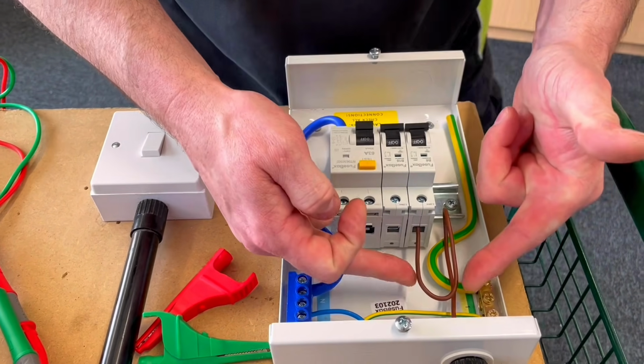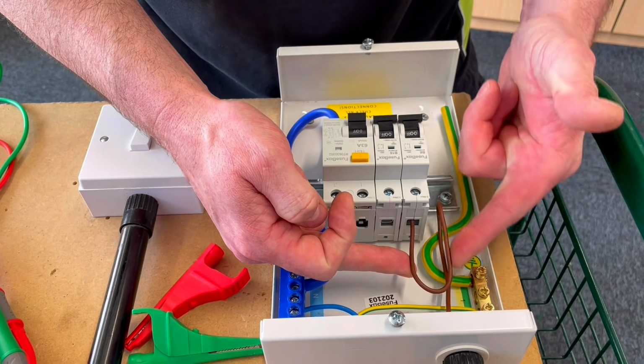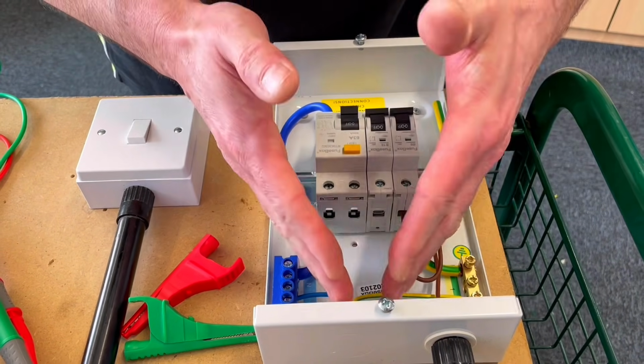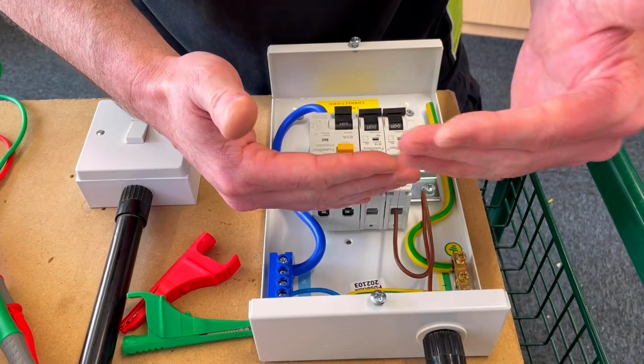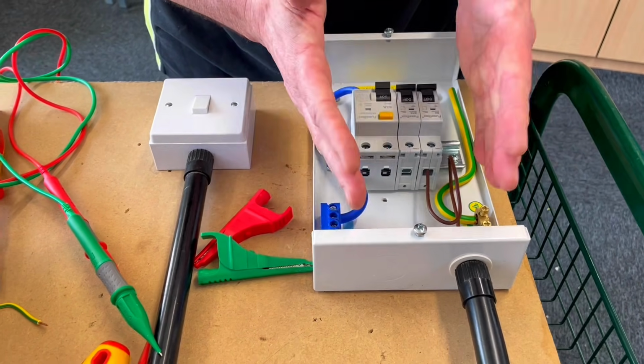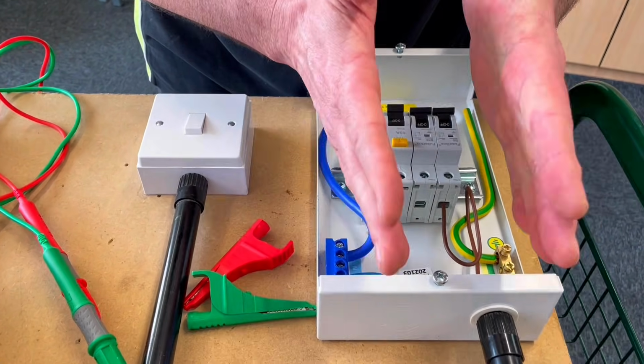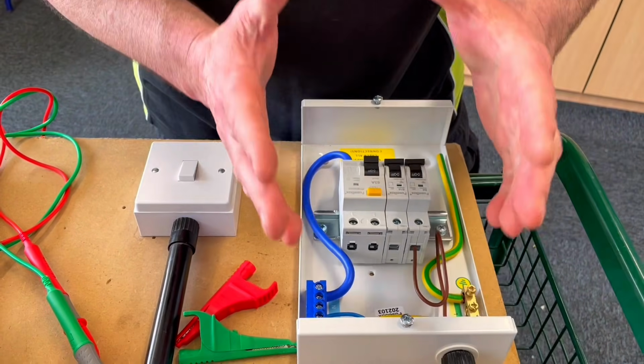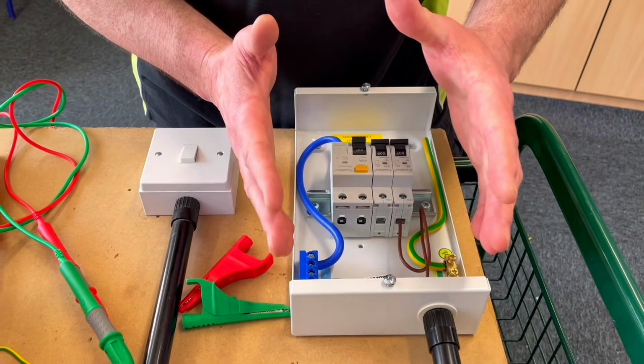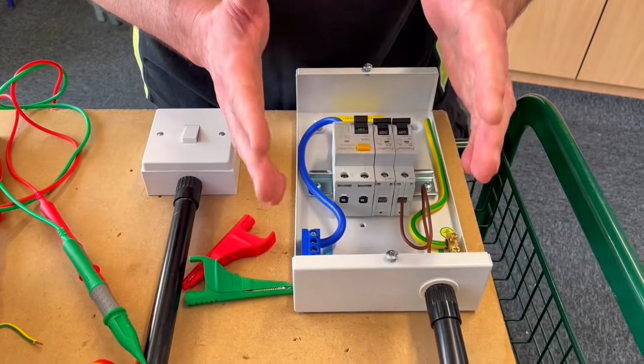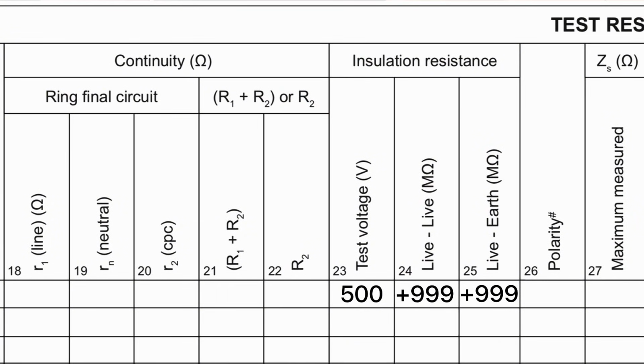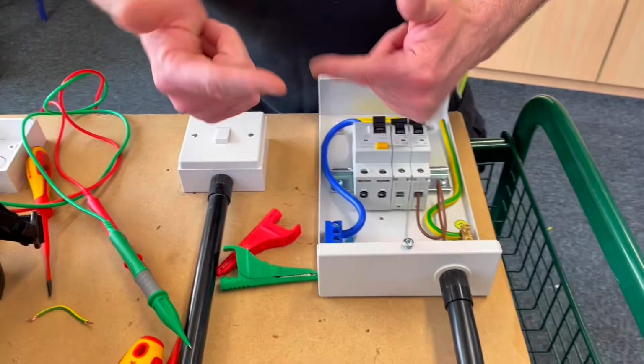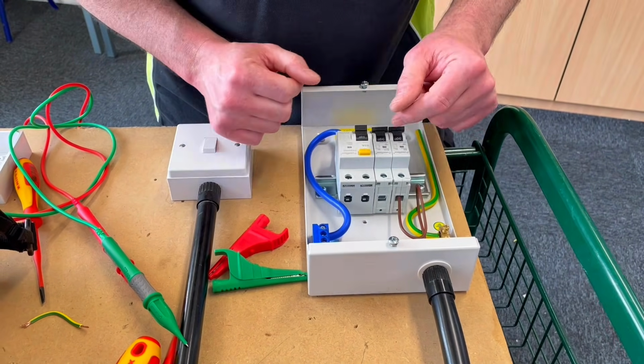And we would expect this reading to be massively high. So what we're trying to prove is that the insulation around our conductors has not degraded between them. So we don't expect these to have broken down over time, or perhaps friction caused them when pulling in to rub against each other, and the insulation between it is starting to break down. These are brand new cables. We expect it to be a fantastically high reading, and we got a reading higher than the machine could read, and we would record those readings for me as plus 999. But sometimes people use that greater than symbol. But again, I like to put plus in there. So that's the insulation resistance test carried out.